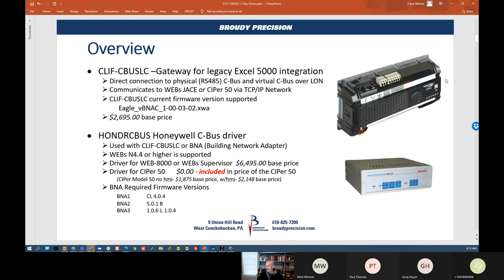Just as an overview, this is the CLIF device. Those of you that know the CIPer 50 — it's basically the same housing style and size as a CIPer 50 controller. It has two RS-485 ports on it, but only the first port is used for the CBUS. The CLIF device is a gateway for bringing in the XL5000 devices with physical 485 or virtual CBUS over LON. This device will talk over the network over IP to the CIPer 50, or it can be used with the Webs JACE device or a Webs Supervisor as an enterprise driver. There is firmware available to get the CLIF device to the right level to work with the XL5000.